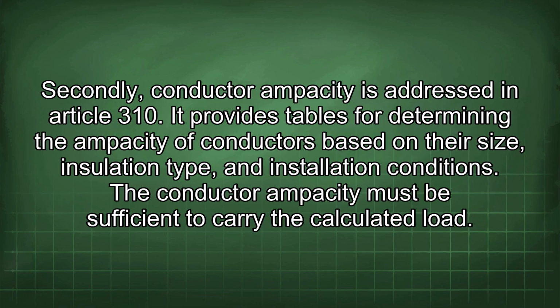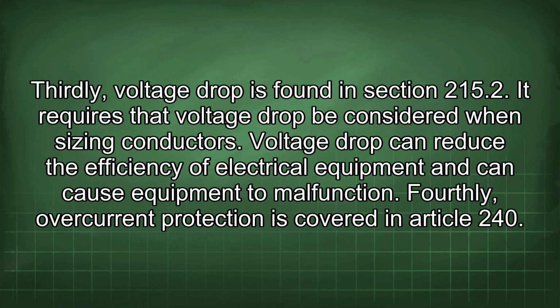Secondly, conductor ampacity is addressed in Article 310. It provides tables for determining the ampacity of conductors based on their size, insulation type, and installation conditions. The conductor ampacity must be sufficient to carry the calculated load. Thirdly, voltage drop is found in Section 215.2. It requires that voltage drop be considered when sizing conductors. Voltage drop can reduce the efficiency of electrical equipment and can cause equipment to malfunction.